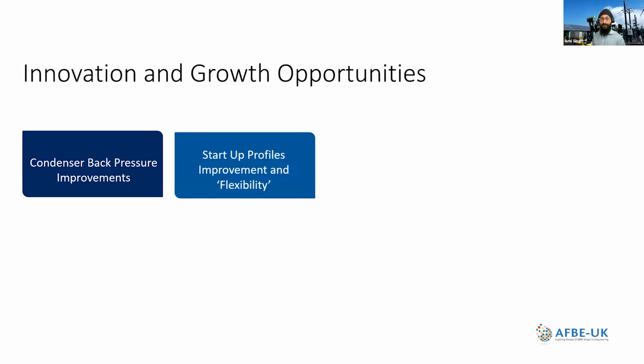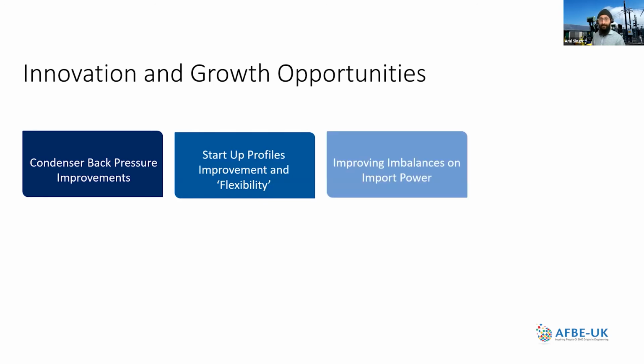Our flexibility has improved significantly over the last 3 years. For example, a cold start used to take approximately 9 hours; now we've shaved off approximately 2.5 hours from that. Our warm start has also seen significant improvements. All these stats are based on the hot metal temperatures on our steam turbines, which are a limiting factor.